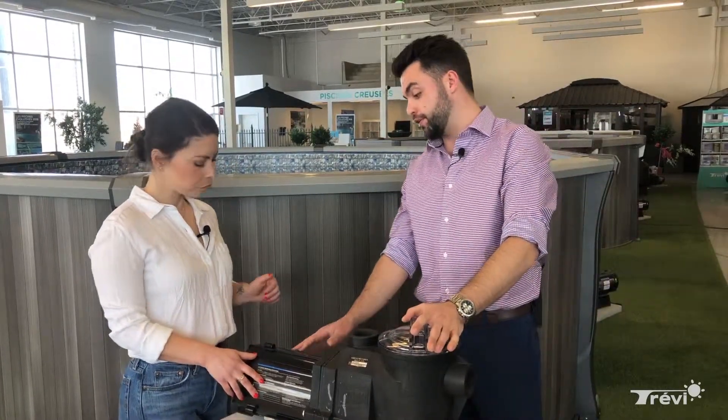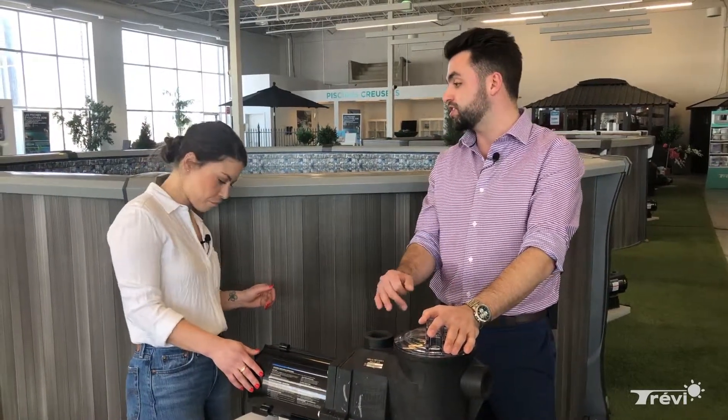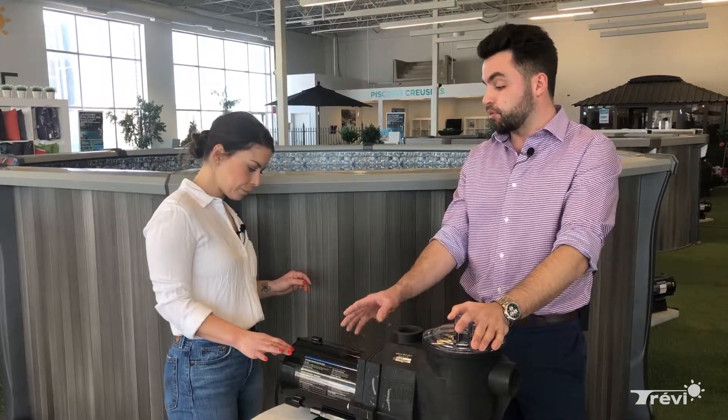To program it, you're gonna go to the switch at the back and look at it. It's a rocker switch with three positions: the lower position is on, the middle position is off — which we're in right now — and the top position is program. Go ahead and click it to the top position.